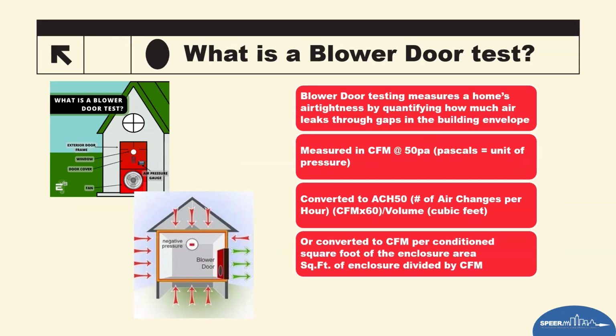Why are we doing this? Yes, we're measuring the air leakage in the building, but why? I mean, it's a good rule of thumb to measure the air leakage to determine how leaky the house is. But what does that tell us? It tells us that the air inside the building is not going to overturn drastically, so we're not going to have to keep conditioning it. So it rolls back into sizing.